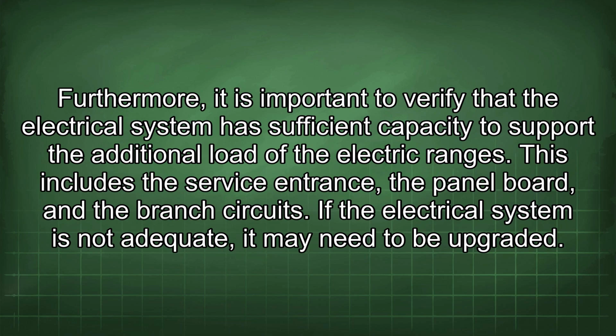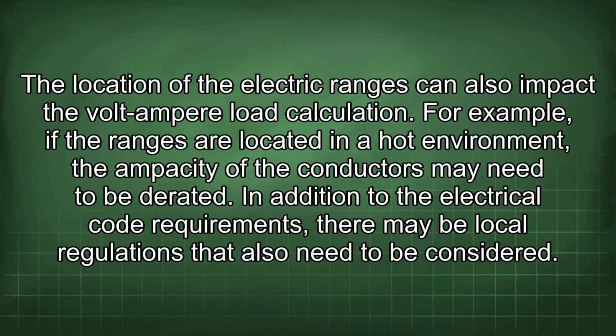Furthermore, it is important to verify that the electrical system has sufficient capacity to support the additional load of the electric ranges. This includes the service entrance, the panel board, and the branch circuits. If the electrical system is not adequate, it may need to be upgraded. The location of the electric ranges can also impact the volt-ampere load calculation. For example, if the ranges are located in a hot environment, the ampacity of the conductors may need to be derated.